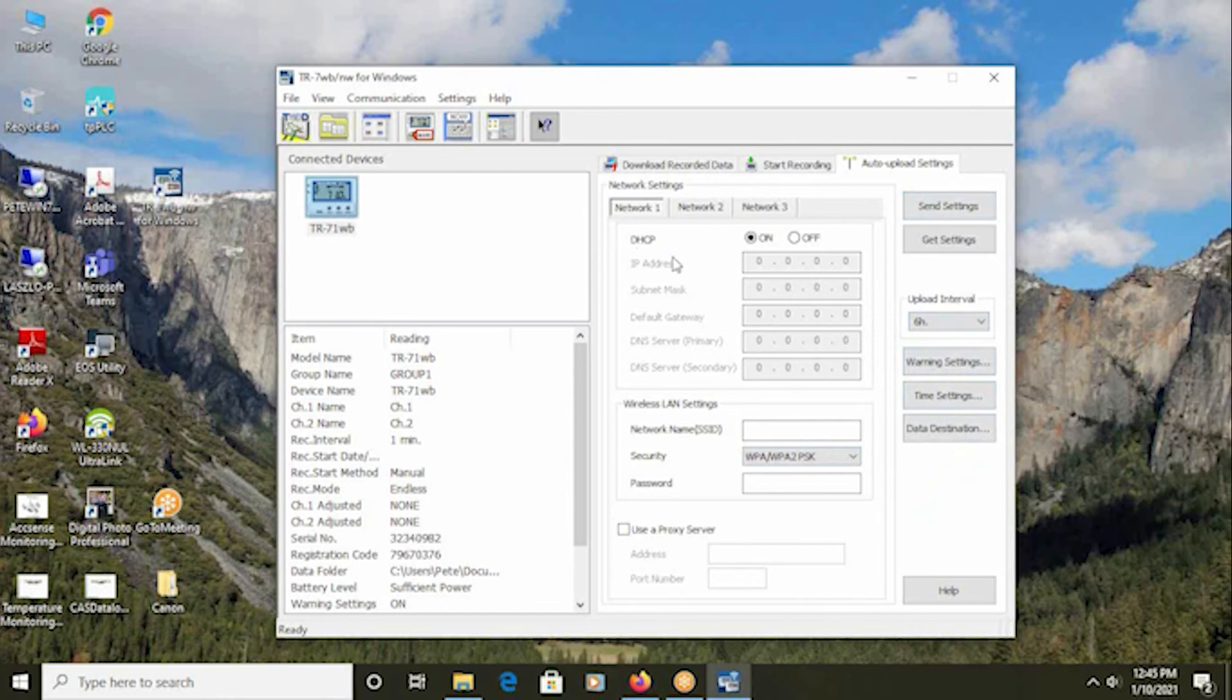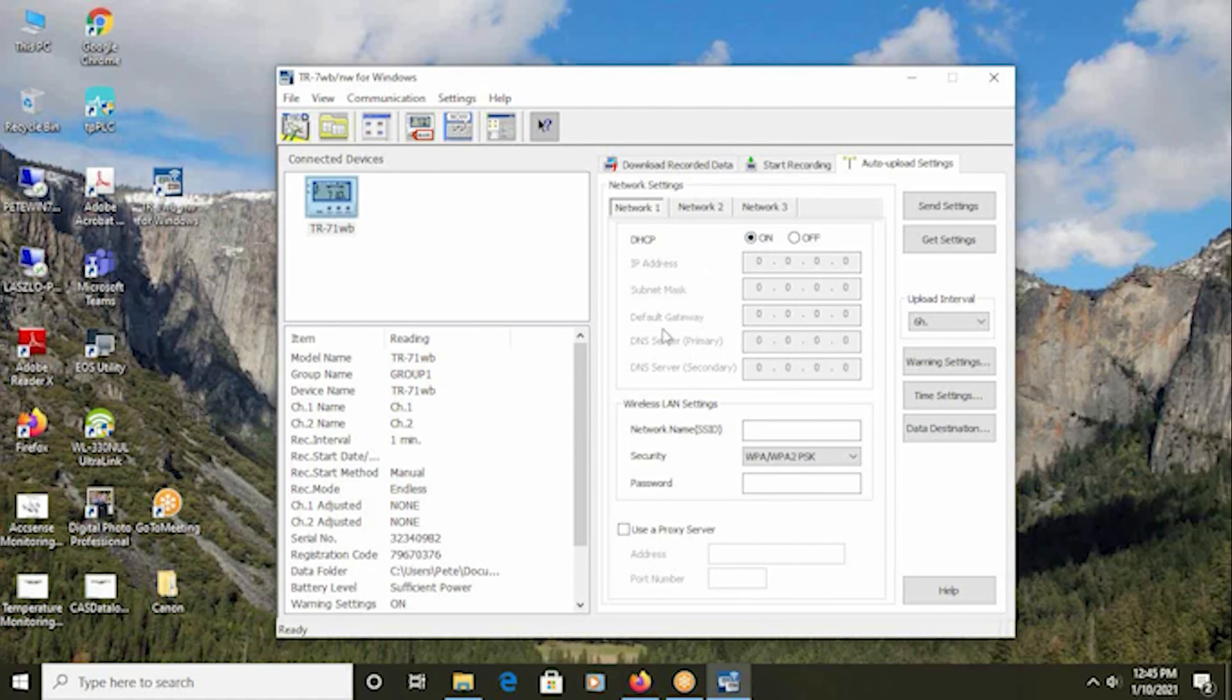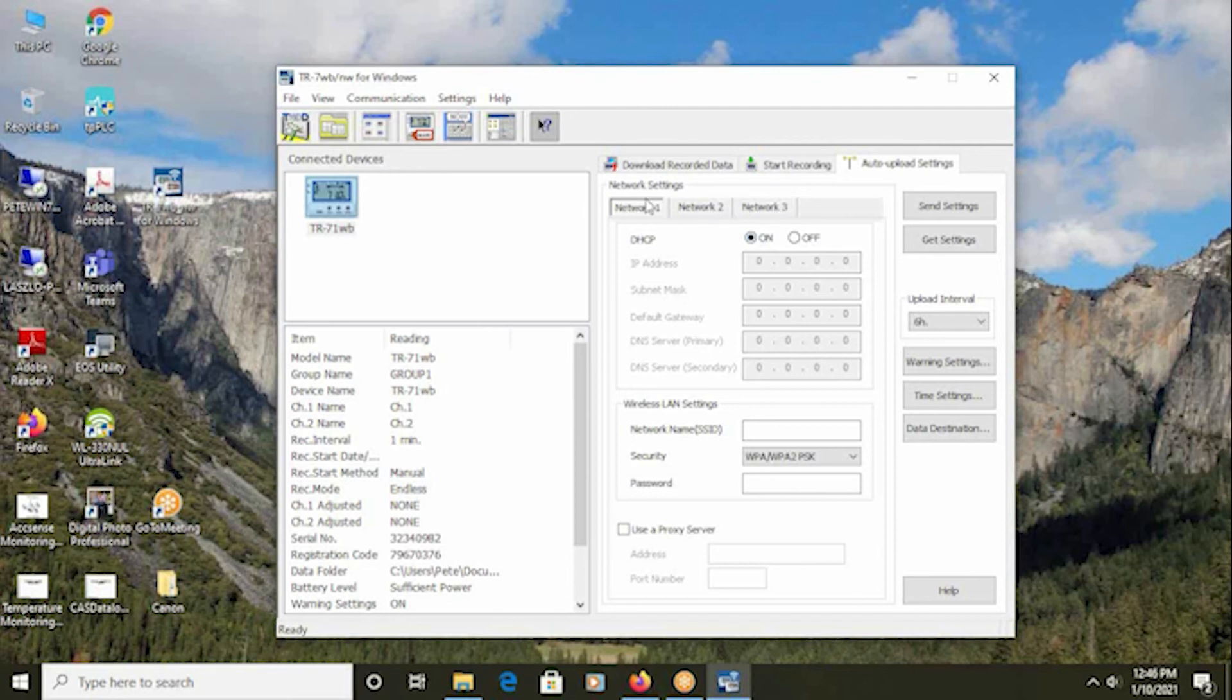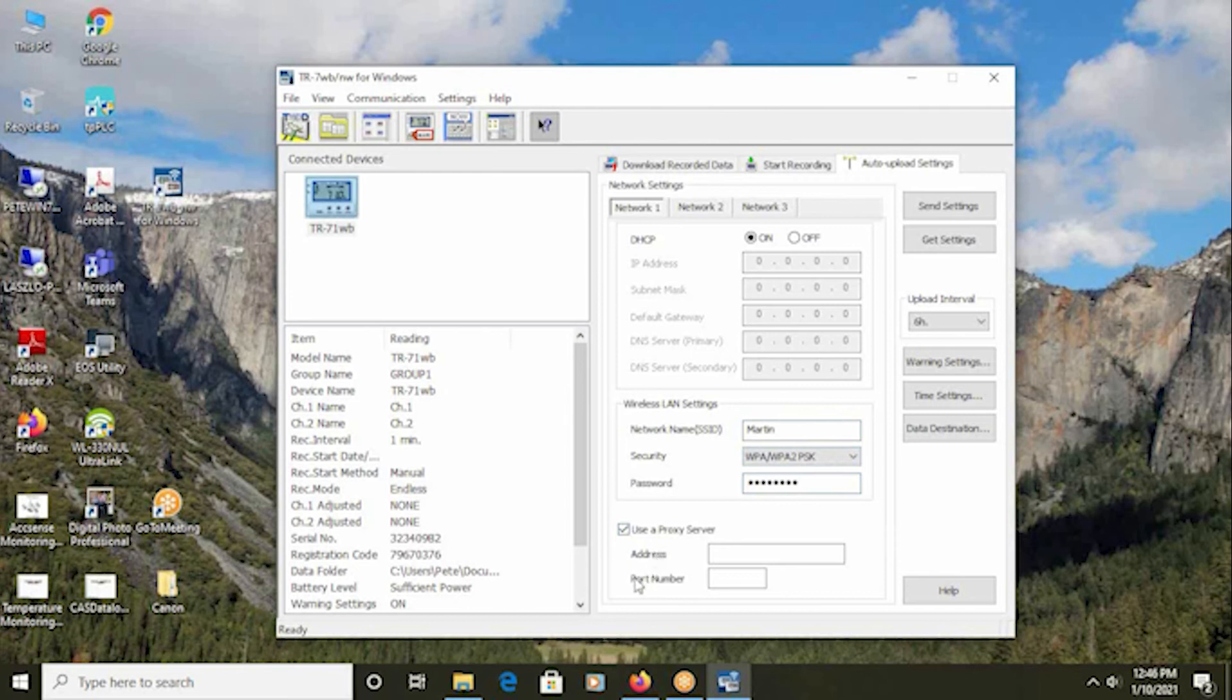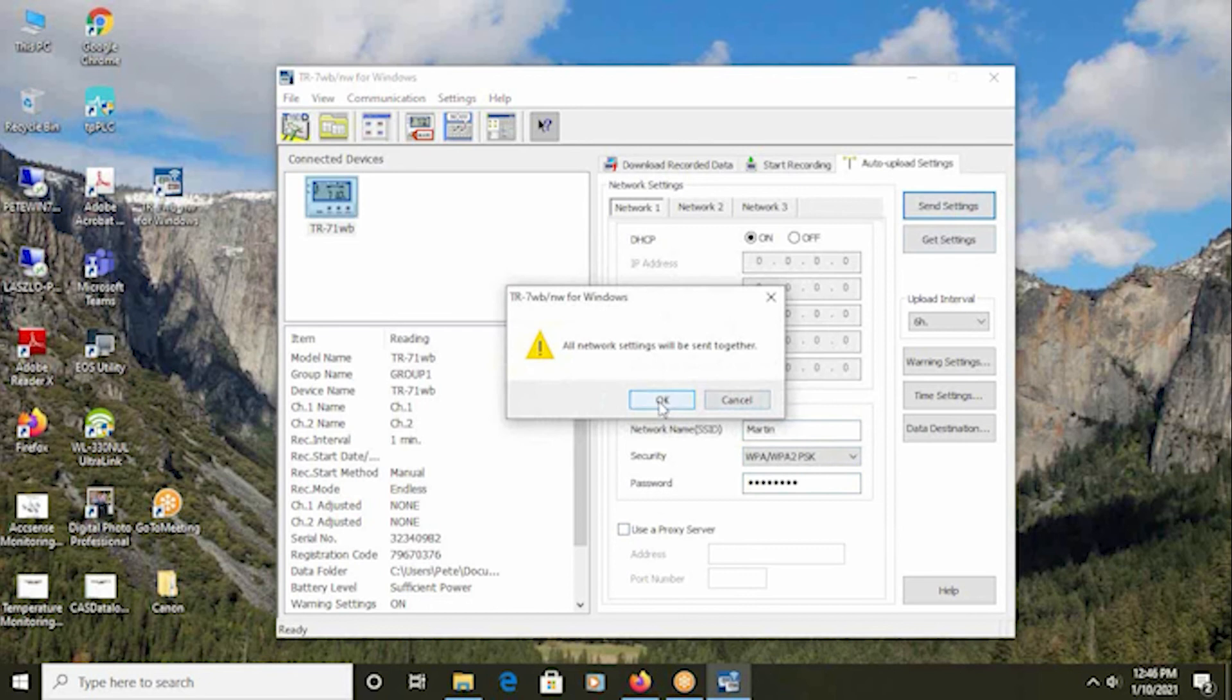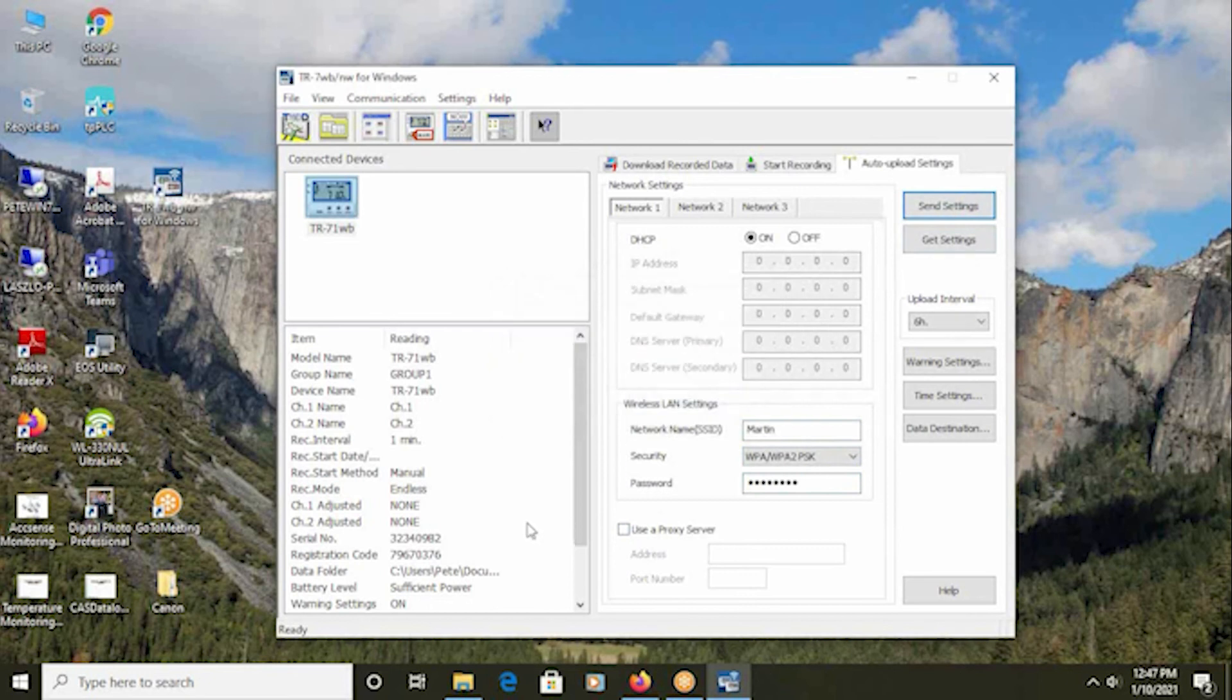Most people would choose DHCP with the radio button clicked to on to allow the Wi-Fi access point and the router assembly to send the IP address and all the addresses of the related IT devices to configure the logger. The logger can connect to up to three available Wi-Fi networks, so if there are backup or emergency networks or if the logger will be moving through different network areas. Choose the network name or SSID that's available. Choose the security type and enter in the password. If you use a proxy server in your organization, enter in the IP address of the proxy server and the port number. Again, remember to send the settings. When you're done with the settings, you should leave the USB connected for now or you can remove it as you wish.